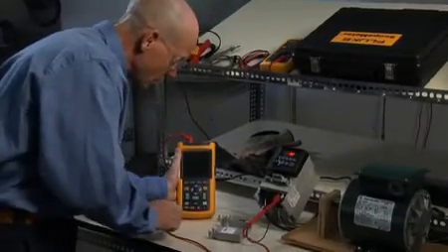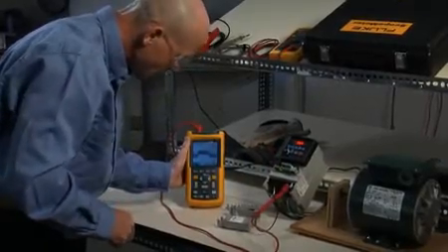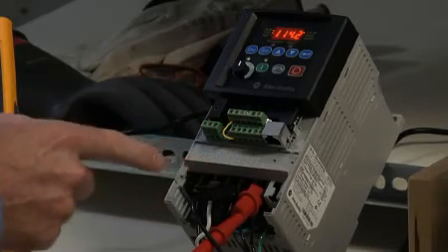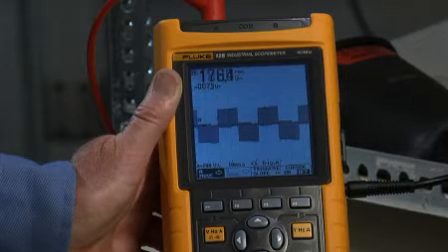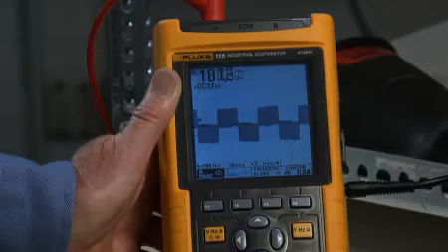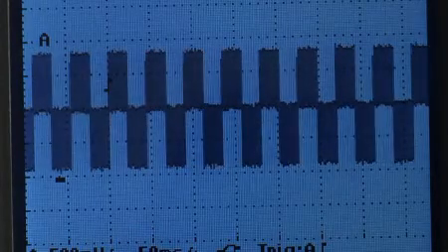Instead, we use an oscilloscope to check the voltage of the motor terminals. Connecting the scope between phase L1, L2, or L3, we can clearly see the impact of improper cabling or motor insulation by comparing an ideal signal with the signal where the effect of reflections creates high voltage transients.